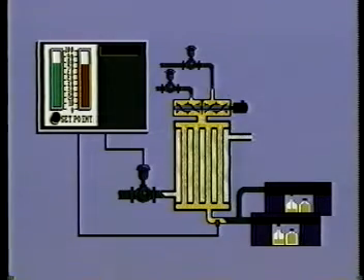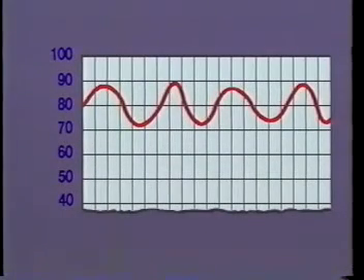When the installation was complete and the process was started, they realized that the metering of the raw materials was highly successful. The mechanical mixing was better than expected. The heat exchanger performed admirably, and the controller opened and closed the new steam valve. But look what happened to the temperature record. The temperature would first increase to 90 degrees and then fall to 70 degrees.